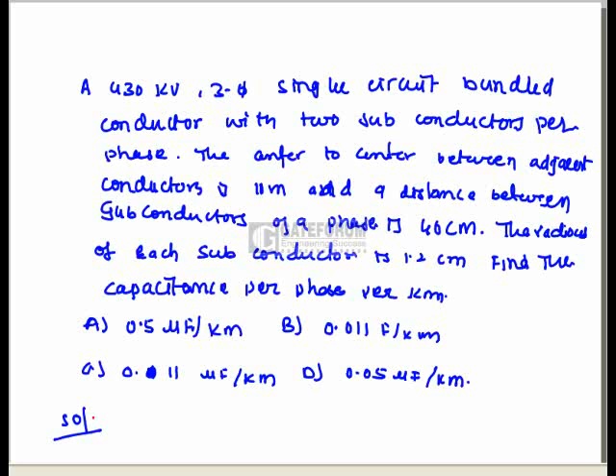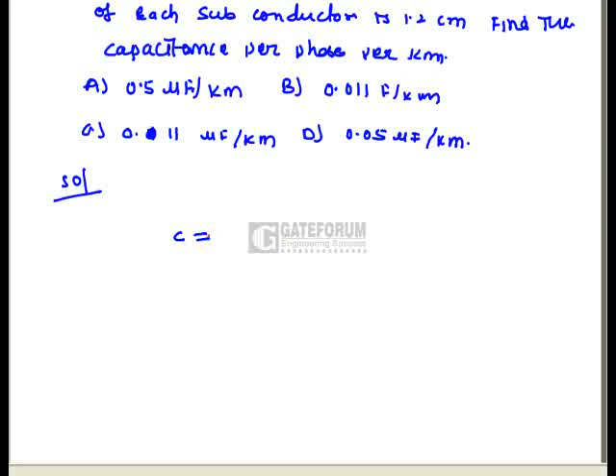The next problem: a 430 kV three-phase single-circuit bundle conductor with two subconductors per phase. The center-to-center distance between adjacent conductors is 11 meters, the distance between subconductors of a phase is 40 centimeters, and the radius of each subconductor is 1.2 centimeters. Find the capacitance per phase per kilometer. The question looks complex but the answer is straightforward. The capacitance per phase formula is C = 2πε₀ / ln(GMD/GMR) farads per meter.